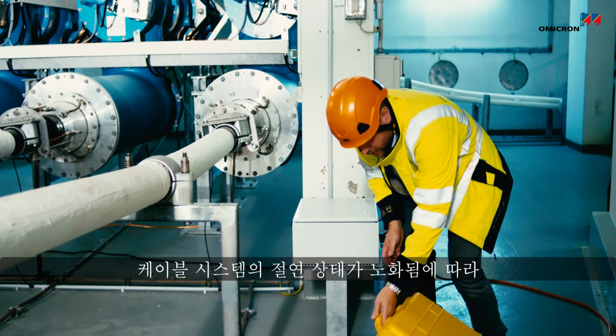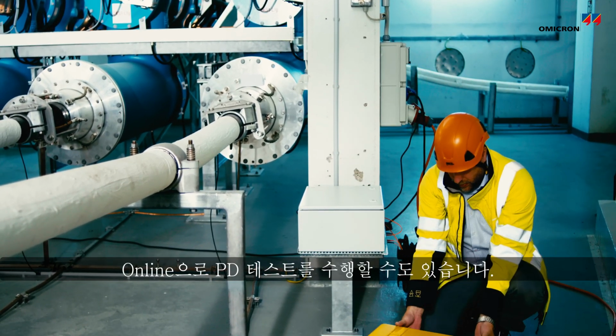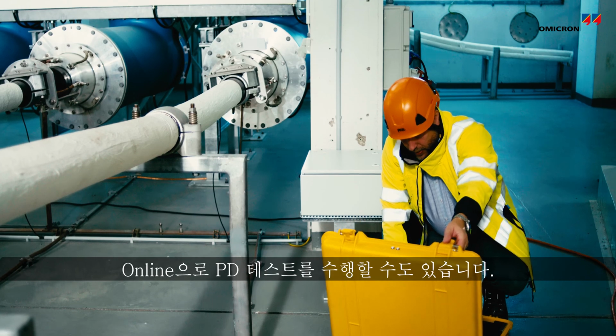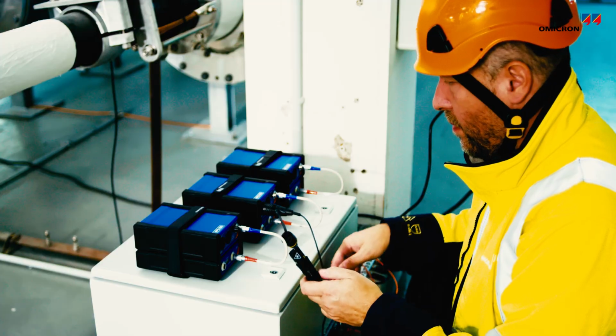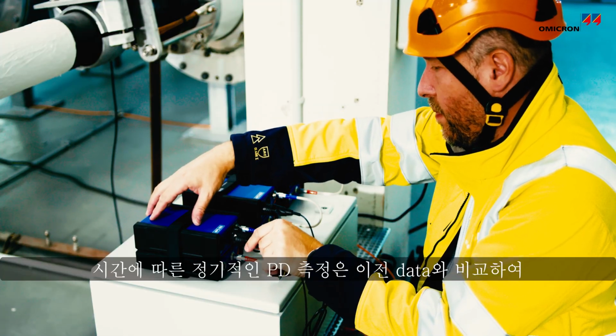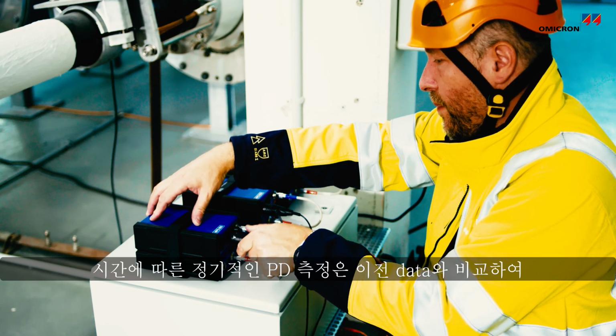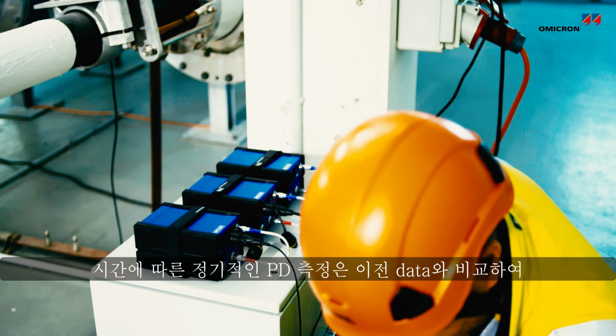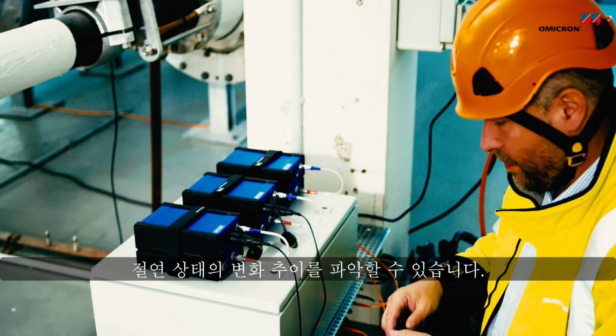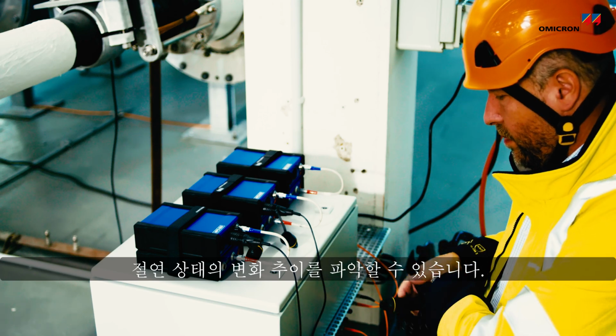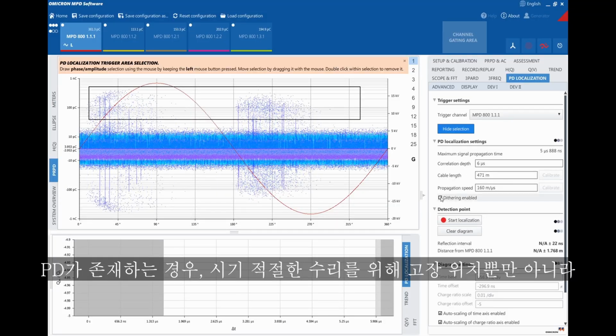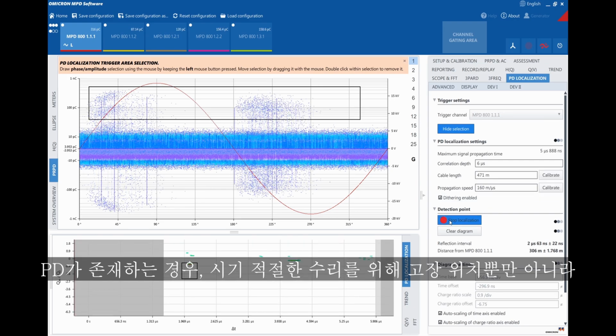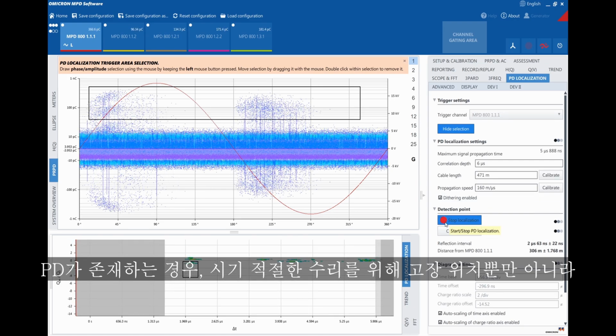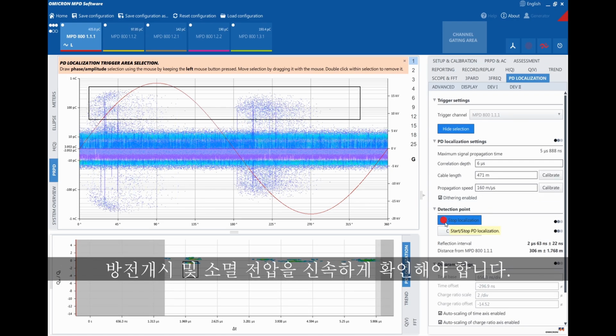In-service PD testing can also be performed to assess the dielectric condition of the cable system as it ages. Regular PD measurements over time can be compared to previous measurements to trend insulation condition. If PD is present, then the inception and extinction voltage as well as the fault location need to be quickly determined to make timely repairs.